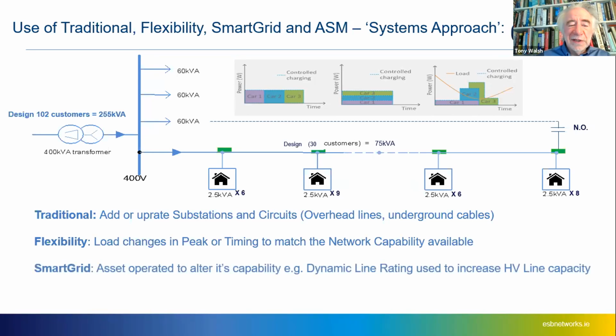Smart grid, which you've heard people talk about innumerable times, is really about the assets. If you change how the asset operates, or change how you control its capability, that gives you something extra—for instance, dynamically rating a piece of equipment. You may have a substation rated at 400 kVA continuously, but by monitoring it, you might allow it to increase its load to 480 kVA because you know it'll cool down later, and you dynamically rate it as a 480 kVA transformer instead of a 400 kVA one. That's essentially what smart grid is.